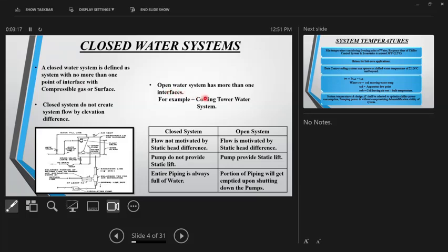Now, if you imagine a cooling tower circuit, which are the two surfaces which are open? One where the nozzle comes from the top, there it actually gets exposed to the atmosphere, and the second surface is in the basin, where basin water is exposed to atmosphere. So there are more than one points which are open to atmosphere. That's how, by definition, cooling tower systems are open. Is this clear to all? What is the basic difference between open and closed? Yes, sir. A closed water system has only one interface, whereas open systems will have more than one.